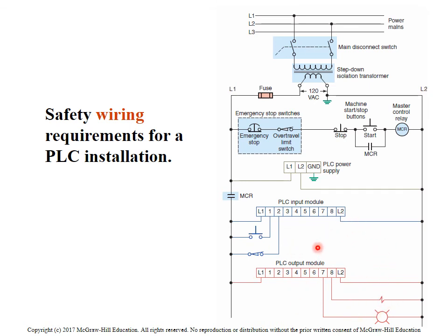Now, it's been my experience that most of the time they're just removing output power. In very rare cases, they remove the input power. Most of the time it's just output power because it's output power that creates the motion. It turns on the valves, turns on the motors, turns on all these devices that create motion, and that's what we're trying to avoid.